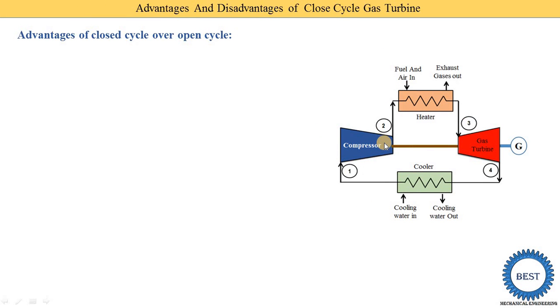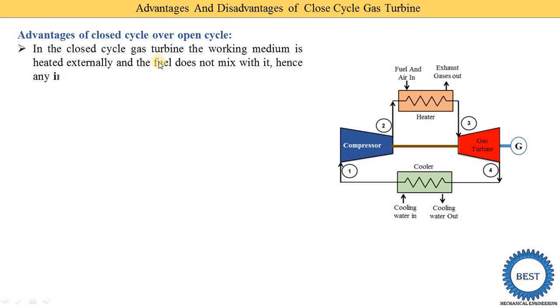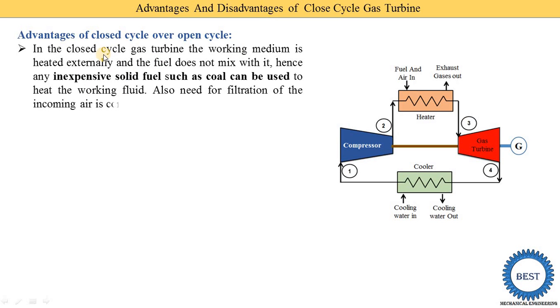Here is the image of a closed cycle gas turbine power plant. The first advantage is that in the closed cycle gas turbine, the working medium is heated externally. Here you can see in this heater, the working medium coming from the compressor is passed through this tube, and outside the tube the combustion of the fuel is carried out. It is called externally heated because the fuel and the working substance are not mixed.